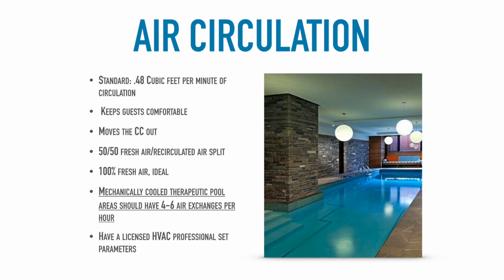Now, for all of us who have indoor pools, don't start feeling guilty about this. Realistically, all of our pools would smell like this if we had no air circulation. The reason why you're smelling more chloramines inside of those indoor facilities is because we simply need to bump up our air circulation a little bit more to blow it out, and we'll be just fine. A 50-50 fresh air and recirculated air split is a minimum requirement for our air circulation, and 100% fresh air is ideal. Outdoor pools, you got that like no one's business.